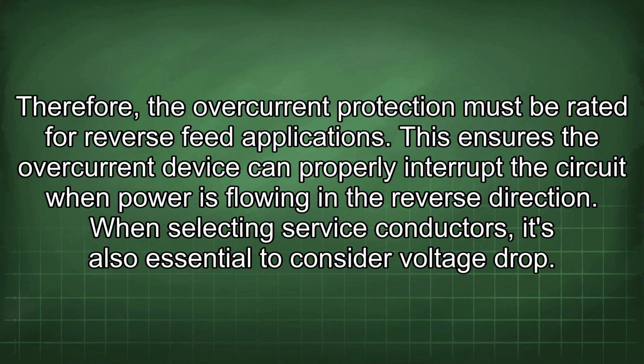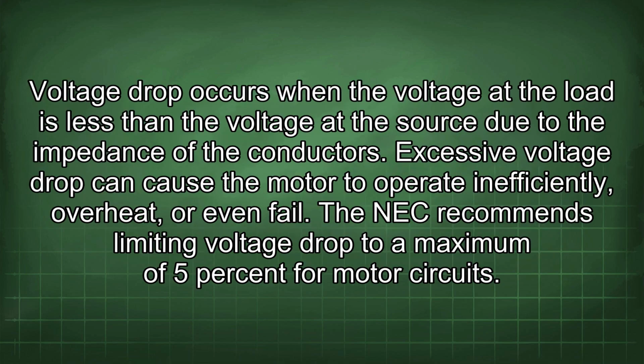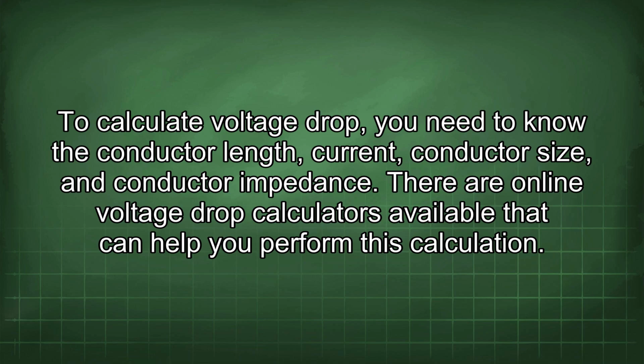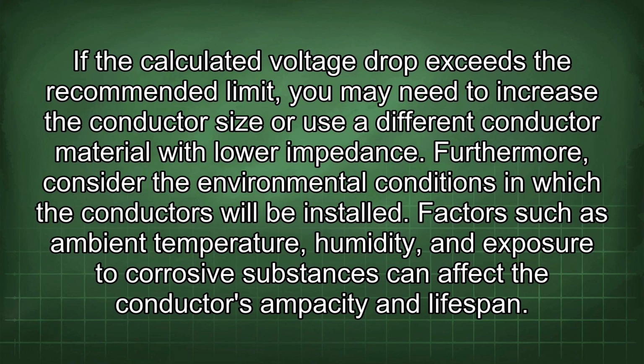When selecting service conductors, it's also essential to consider voltage drop. Voltage drop occurs when the voltage at the load is less than the voltage at the source due to the impedance of the conductors. Excessive voltage drop can cause the motor to operate inefficiently, overheat, or even fail. The NEC recommends limiting voltage drop to a maximum of 5% for motor circuits. To calculate voltage drop, you need to know the conductor length, current, conductor size, and conductor impedance. There are online voltage drop calculators available that can help you perform this calculation. If the calculated voltage drop exceeds the recommended limit, you may need to increase the conductor size or use a different conductor material with lower impedance.